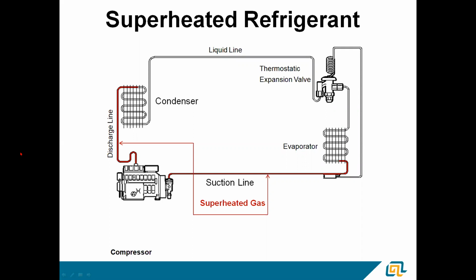Discharge line of the compressor would also have superheated vapor. Discharge temperature off the compressor shouldn't really exceed 180 degrees. If I saw temperatures of 180 degrees or higher, I kind of start getting a little nervous and checking things over, making sure everything else is correct.